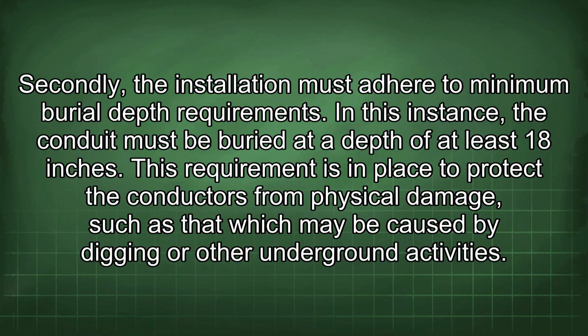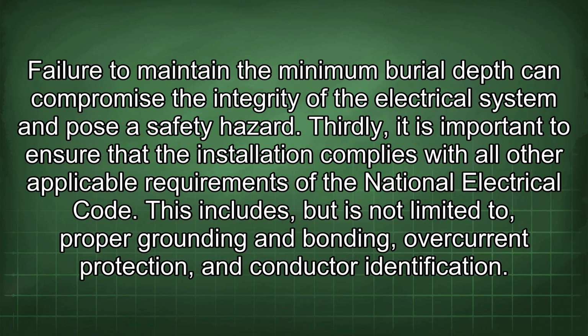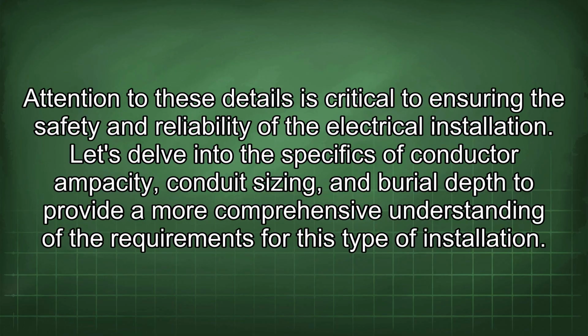This requirement is in place to protect the conductors from physical damage, such as that which may be caused by digging or other underground activities. Failure to maintain the minimum burial depth can compromise the integrity of the electrical system and pose a safety hazard. Thirdly, it is important to ensure that the installation complies with all other applicable requirements of the National Electrical Code. This includes, but is not limited to, proper grounding and bonding, overcurrent protection, and conductor identification. Attention to these details is critical to ensuring the safety and reliability of the electrical installation.